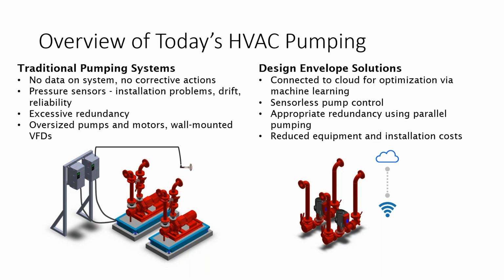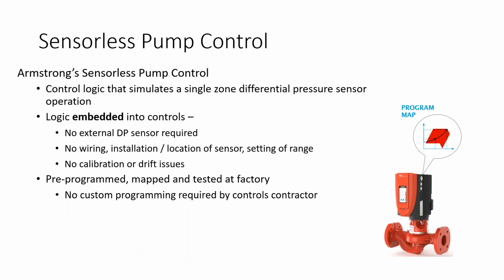So then compare that to a design envelope solution. We'll connect to the cloud for optimization with machine learning. It's a sensorless pump control. It has the appropriate amount of redundancy using parallel pumping and reducing equipment and installation costs. So your first costs are actually reduced right up front. Let's take a look at the sensorless pump control. Armstrong sensorless pump technology is a control logic that simulates a single zone differential pressure sensor operation.